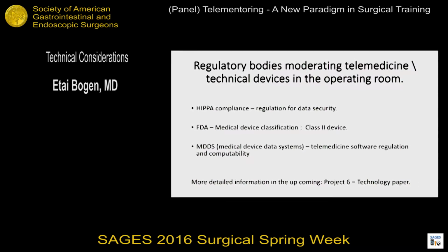And the requirement for a telementoring system is that it has to be a Class 2 device. With regards to the software that's installed both in the operating theater and on the mobile unit, this has a different requirement, and those are the HIPAA and the MDDS compliance requirements.